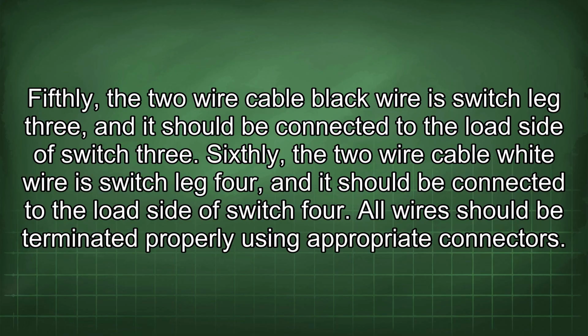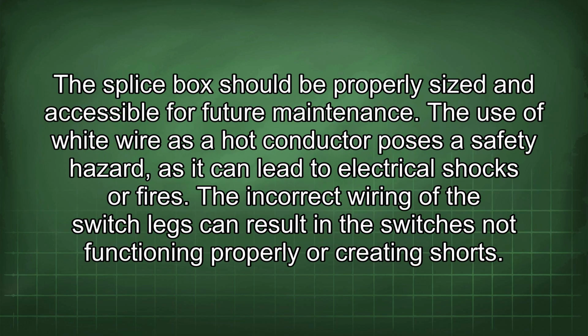Sixthly, the 2-wire cable white wire is switch leg 4, and it should be connected to the load side of switch 4. All wires should be terminated properly using appropriate connectors. The splice box should be properly sized and accessible for future maintenance. The use of white wire as a hot conductor poses a safety hazard, as it can lead to electrical shocks or fires. The incorrect wiring of the switch legs can result in the switches not functioning properly or creating shorts.